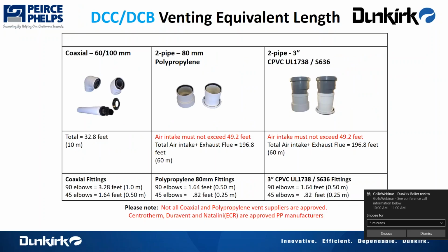Here are our vent runs. The total coax vent run that we can use is about 32 feet, where a 90-degree elbow equates to 3.25 feet. A 45 equates to 1.64 feet.